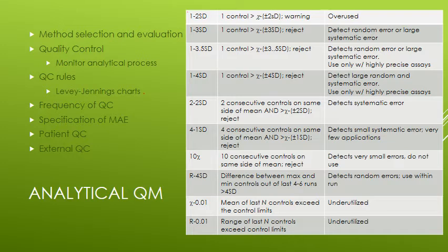Then you're going to have to decide how frequently you're going to test QC with this new procedure. Are you going to do it each shift? Are you going to do it for every test personnel that uses the procedure? How often are you going to do this? Okay. As a general rule, CLSI wants to see you do it more by the throughput instead of by the clock. So maybe you'll run QC every 300 tests or 100 tests to ensure that you catch any errors that might be occurring more rapidly.